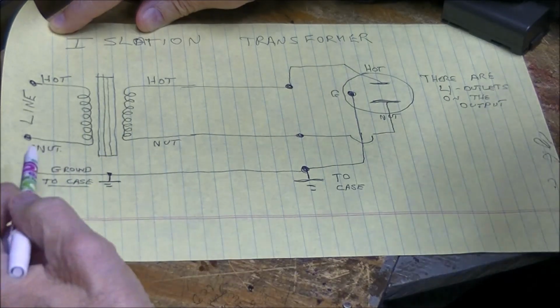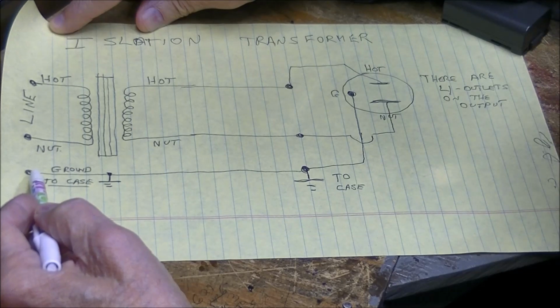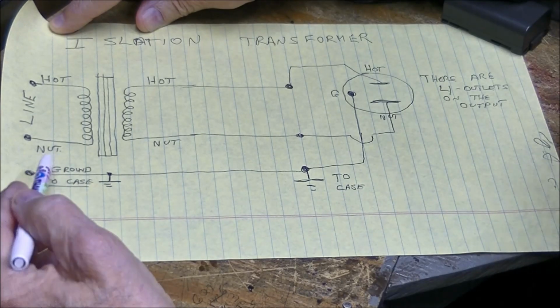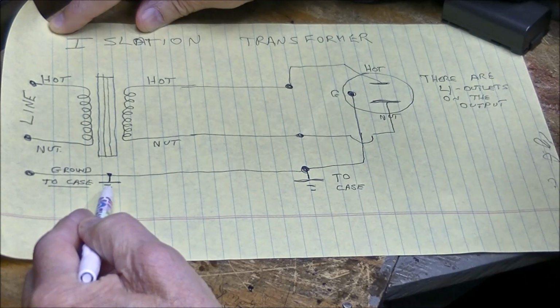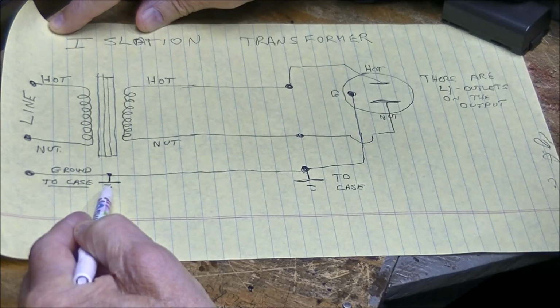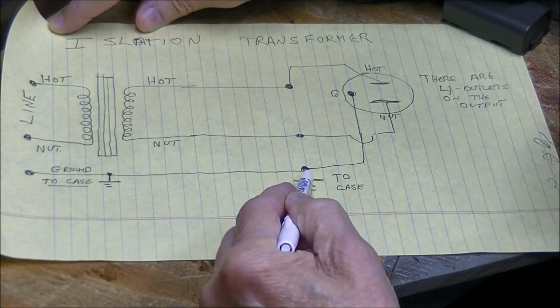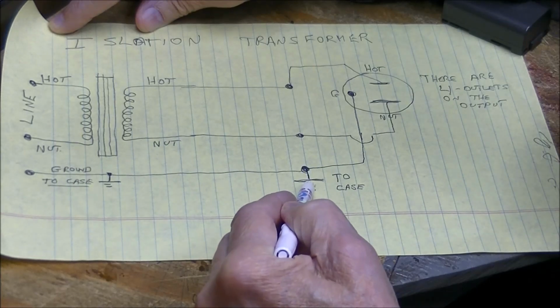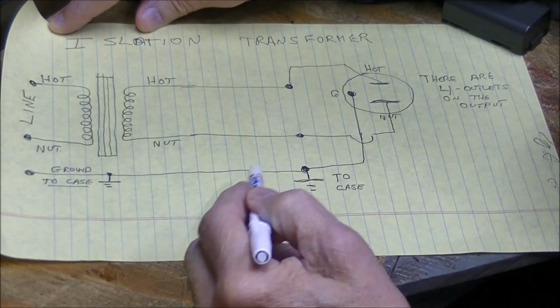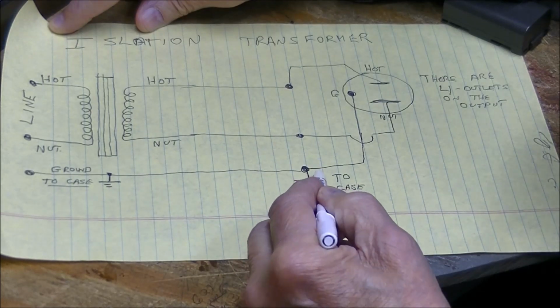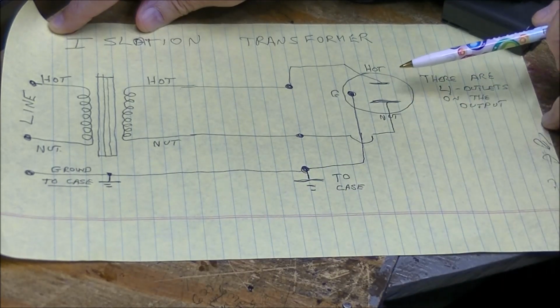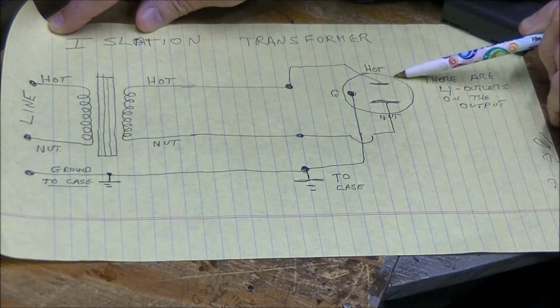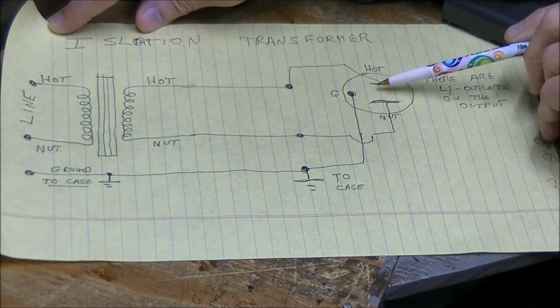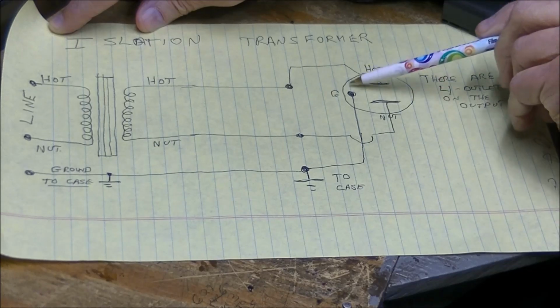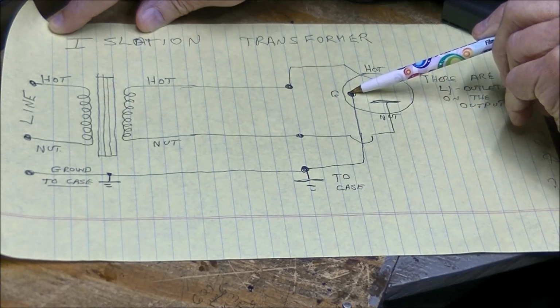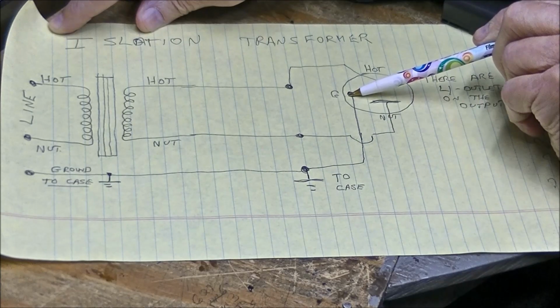First of all, your ground wire, your green wire that comes off the line, is bonded to the case. It continues on, and it is bonded to the case. It's actually bonded to the case in one place, but I drew it over here too. Here's your third prong on the output. There are 4 outlets, and the grounds are all common, bonded to the case.